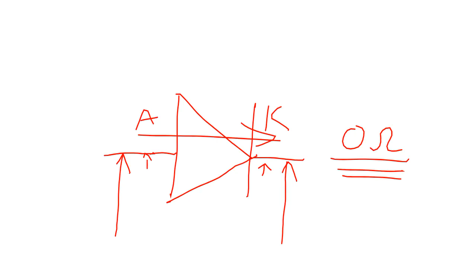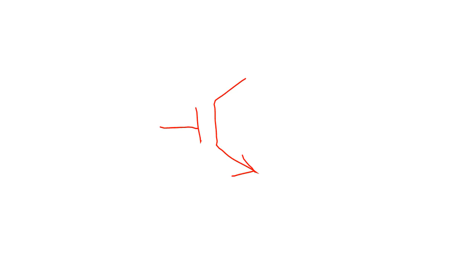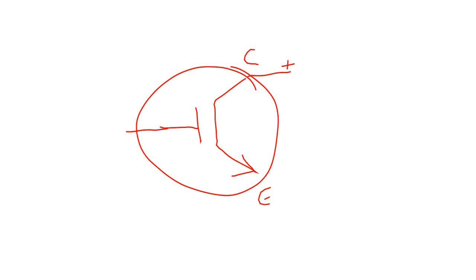All right, let's do an IGBT. So if you have an IGBT, in truth, near enough all IGBTs fail short circuit, and it's usually always between the collector and the emitter, okay? So the easiest way to check is to put your Fluke red lead on the collector and black lead on the emitter, and if you get 0 ohms, once again, you know there is an issue. The problem with IGBTs is that they tend to destroy themselves when they get a short circuit. They're not very good at handling short circuit current, and they physically blow themselves apart.